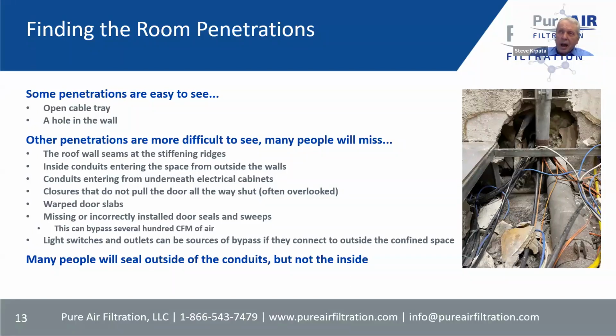The other thing is conduits. Where conduits come into the room, unlike a straight cable tray, people look at those and kind of blow them off. Other people whose room sealing work we've seen might seal or caulk around the outside of the conduit, but almost always they forget about the inside of the conduit. That's a big highway, generally going directly into your electrical equipment, bringing contaminated air from the outside directly onto your equipment. It doesn't get a chance to be filtered first, and that's a huge problem. So you want to seal inside that also and stop that air from coming in.